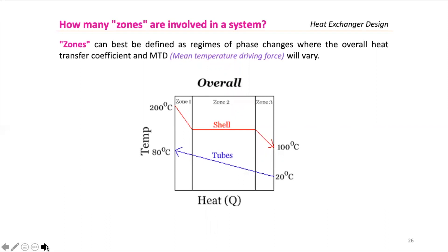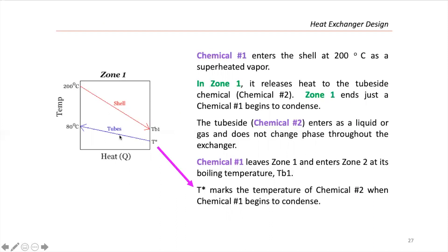When we deal with heat exchangers with phase change — and this is a problem we are going to solve today — the best idea is to divide the problem into zones. We divide the problem into pieces: solve zone one, then zone two, then zone three, or as many zones as you have, and we add the areas. Zones are best defined as regions of phase changes where the overall heat transfer coefficient and mean temperature difference will vary. The strategy is to solve zone by zone.